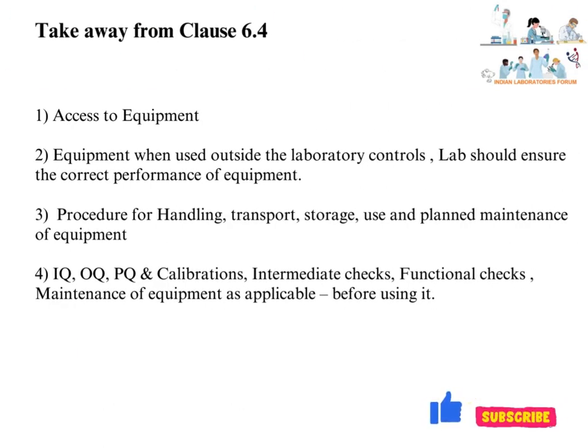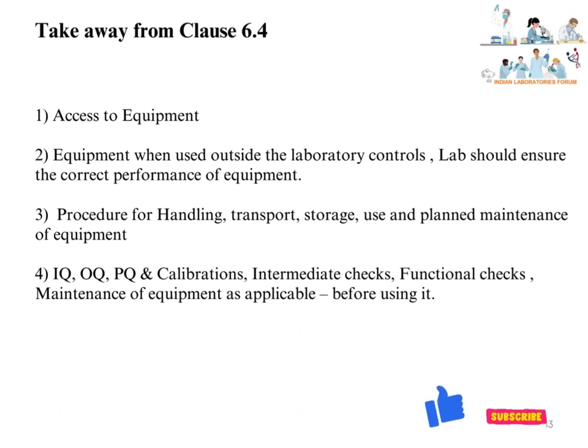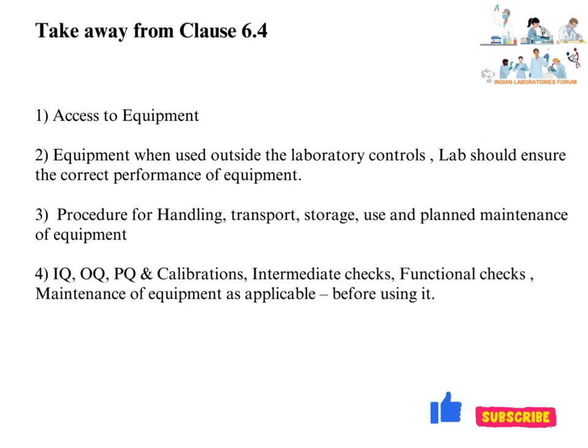Key takeaways from Clause 6.4 of ISO/IEC 17025:2017: Access to equipment should be available. When equipment is used outside laboratory controls, the lab should ensure correct performance. The lab should have a procedure for handling, transport, storage, use, and planned maintenance. Records of IQ, OQ, PQ, calibrations, intermediate checks, functional checks, and maintenance should be available.